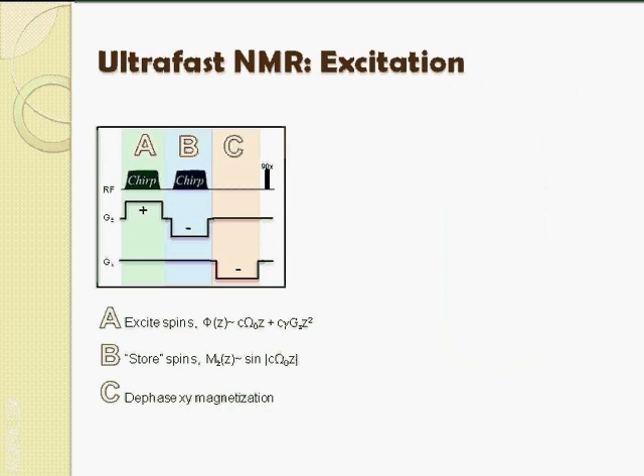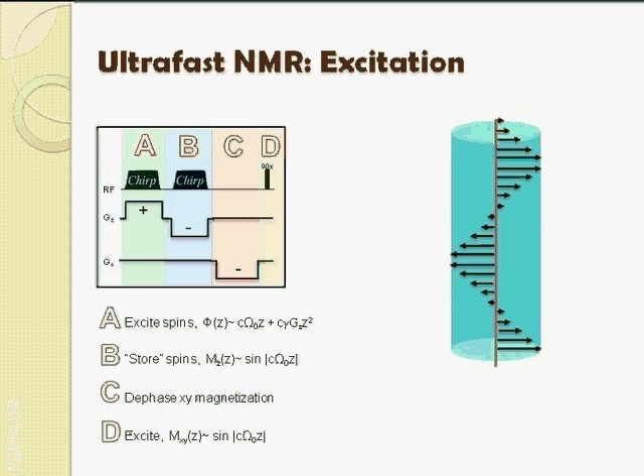Any method of doing so is fine. In this sequence, we've used a strong x-gradient, but you could equally use a strong z-gradient if you lack the appropriate hardware. Now, all we need to do is excite the spins to the x-y plane using a simple 90° hard pulse. Following the hard pulse, the x-y magnetization is proportional to the sine of z and omega-naught. By basic complex algebra, this is equal to the sum of two exponents, both having precisely the phase distribution we are after. We can work with either one. For example, acquiring with a positive gradient at this point will refocus one of them while leaving the other unfocused, dephased, and therefore undetected during our acquisition.